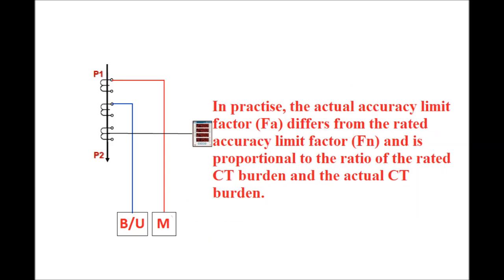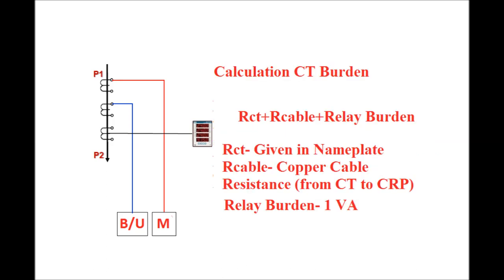In practice, the actual accuracy limit factor FA will differ from the rated accuracy limit factor as defined on the nameplate of the CT. It is proportional to the ratio of the rated CT burden to the actual CT burden. Let us first calculate the CT burden, then we will show how the CT burden depends on the accuracy limit of the protection class CT.